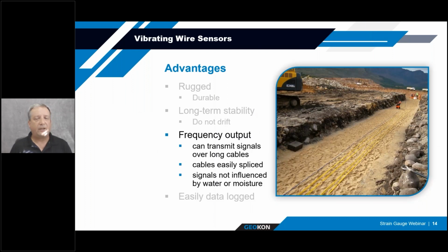Some of the other benefits of vibrating wires is that you can run the signal cables for long distances. Not that you would necessarily want to, but we've done tests in-house where we've had signal cable run for 2 miles without any degradation of the signal from it. The cables can be easily spliced without affecting the performance of the signal as well. And if moisture does get onto the signal leads, it's not an issue unless that moisture does transmit up through the cable into the sensor. But we have had instances where the cable leads are set in a pool of water and you pull them out, shake them off, and take readings, and it's all fine.